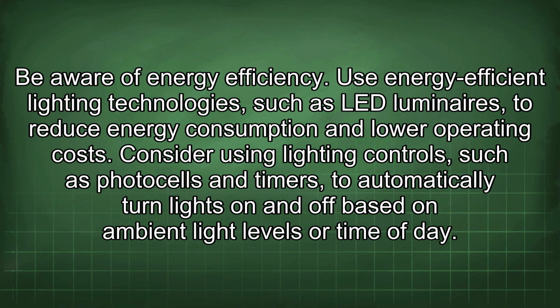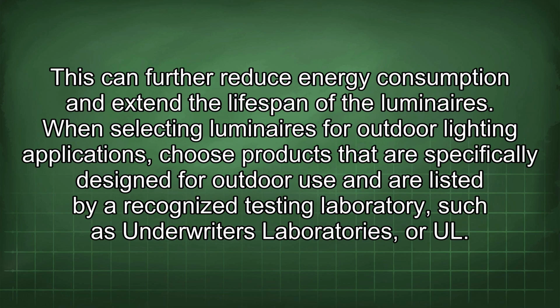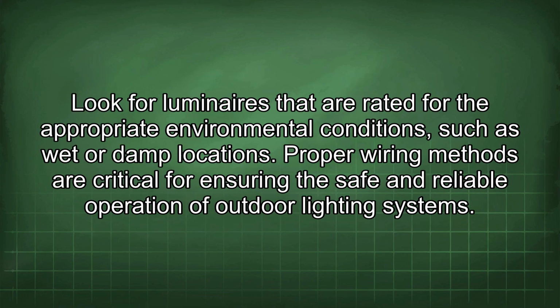Consider using lighting controls, such as photocells and timers, to automatically turn lights on and off based on ambient light levels or time of day. This can further reduce energy consumption and extend the lifespan of the luminaires. When selecting luminaires for outdoor lighting applications, choose products that are specifically designed for outdoor use and are listed by a recognized testing laboratory, such as Underwriters Laboratories, or UL. Look for luminaires that are rated for the appropriate environmental conditions, such as wet or damp locations.